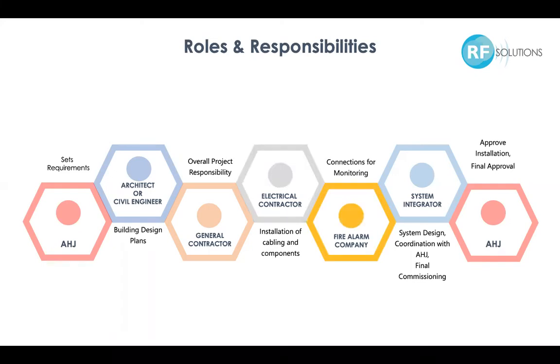The fire alarm company will provide connections if the building's fire alarm monitoring and supervision are extended to include the in-building system. The systems integrator is responsible for designing the system and specifying the proper components. They will coordinate with the AHJ to make sure all requirements are met. And after installation is completed, they will hook up and connect the equipment and perform an extensive coverage test to obtain final approval from the AHJ. The AHJ may coordinate and attend the coverage test performed by the system integrator, and their final approval is required before a certificate of occupancy will be issued.